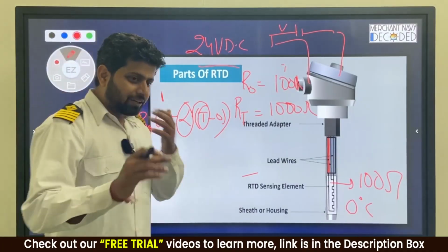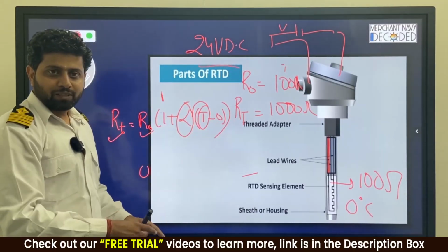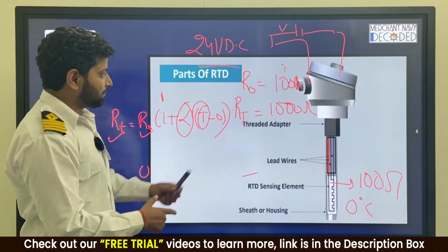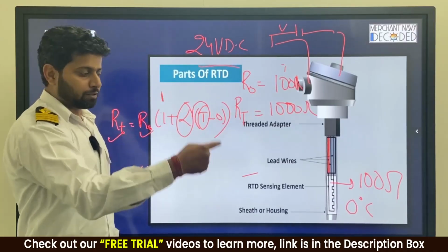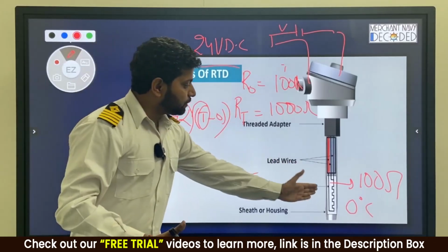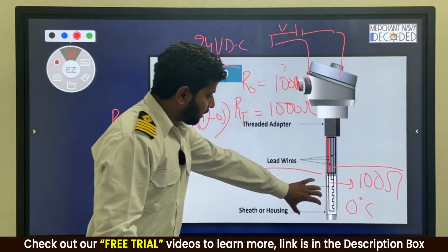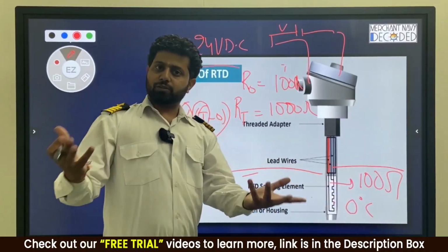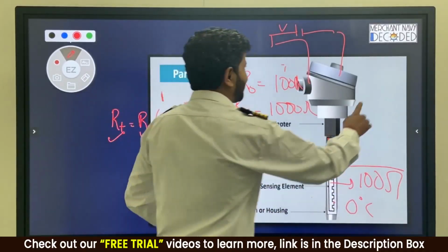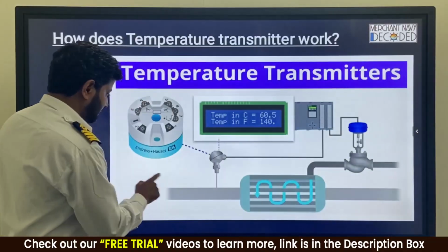Copied, guys? If at all you don't know, can you see on this screen this PT100 chart? You can immediately see over here that if my resistance is this much, how much is the temperature? If my resistance is this much, how much is the temperature? So from here we know, brother, this is inside the main engine exhaust gas and how much temperature is over here. So we know the temperature. Copied, guys? Like in this case, this is fitted inside over here.